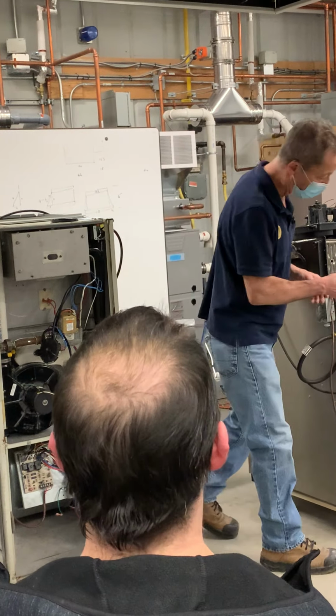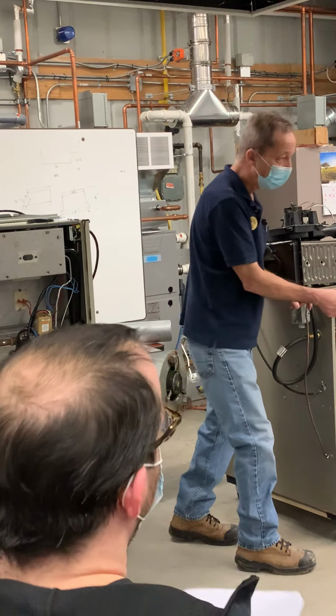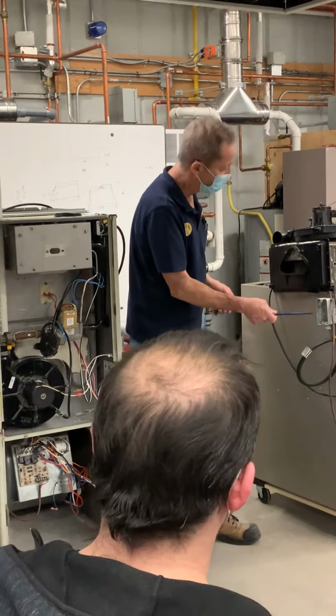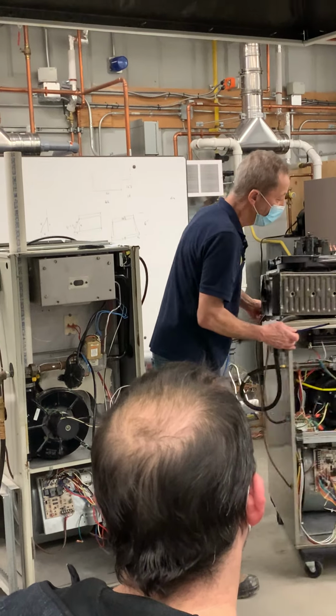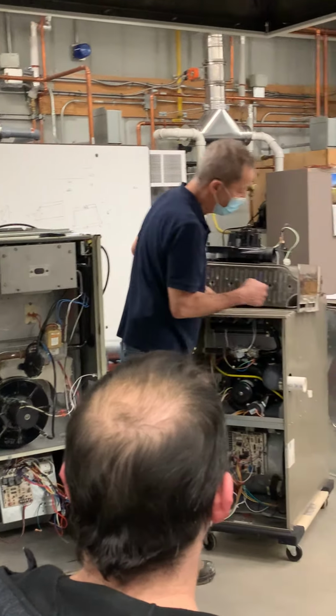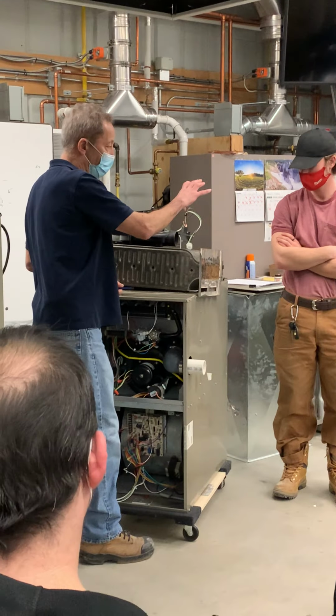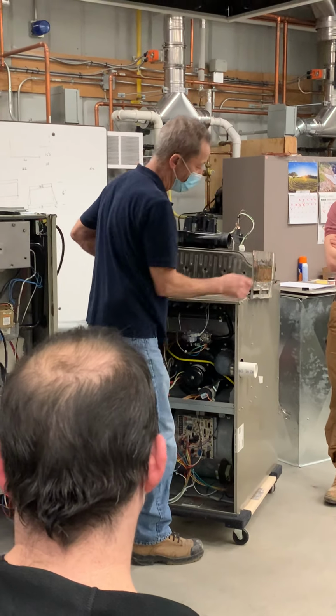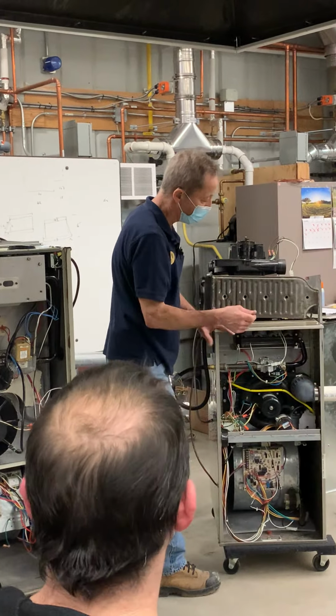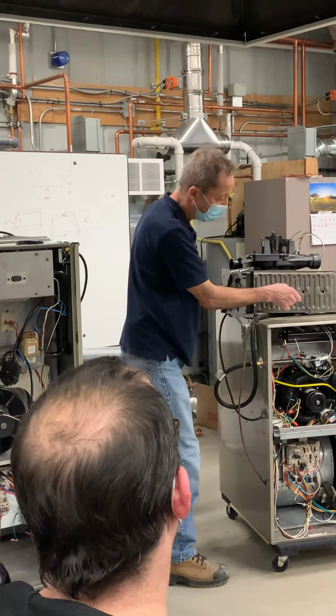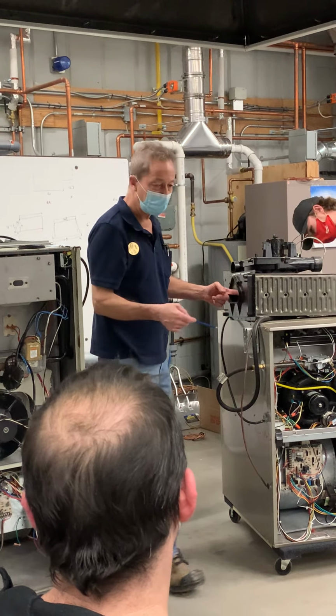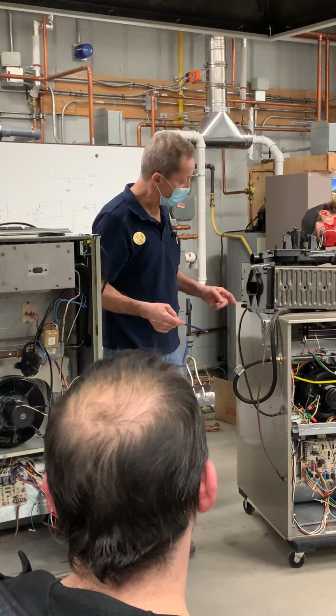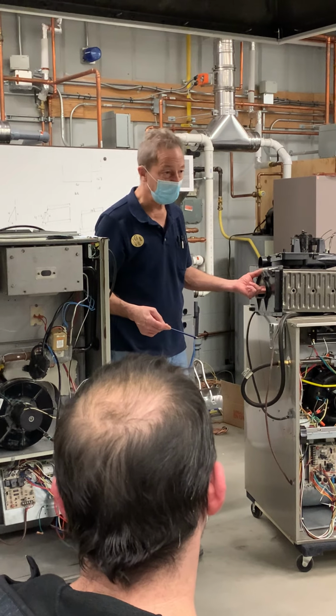It's gotta suck through the primary heat exchanger, through the burners, pull through there, then the outlet for the heat exchanger up here loops and goes in here. So look at the torturous path. I gotta suck all those flue gases through this before it comes here. So it takes a bit of sucking to do that.